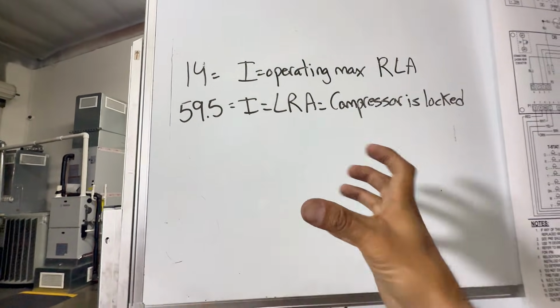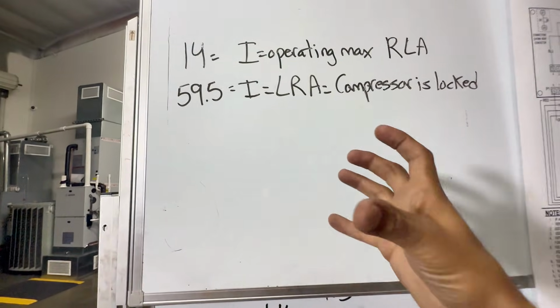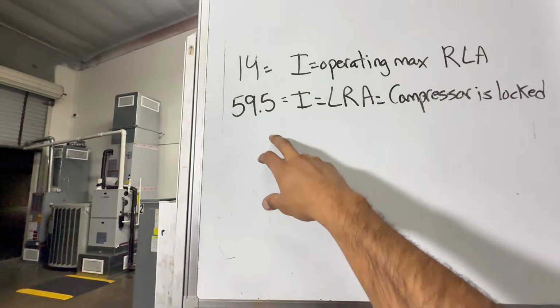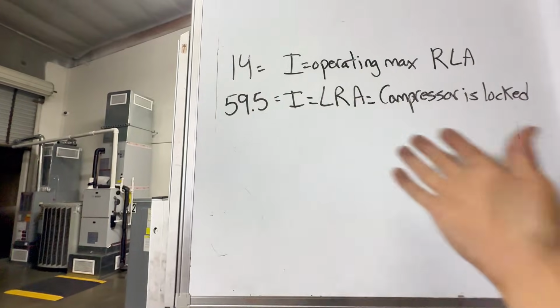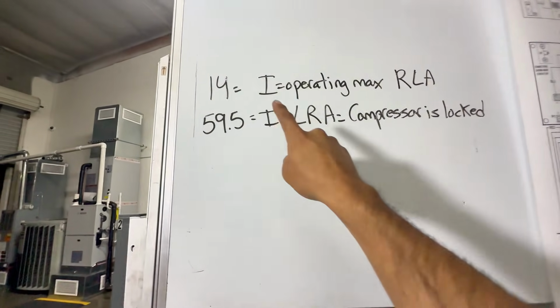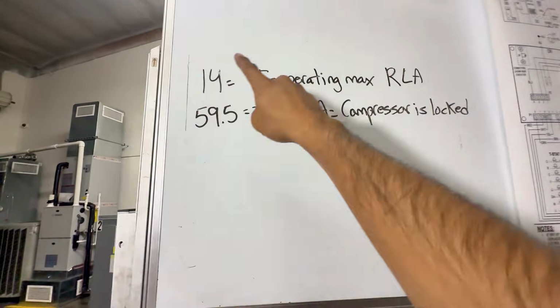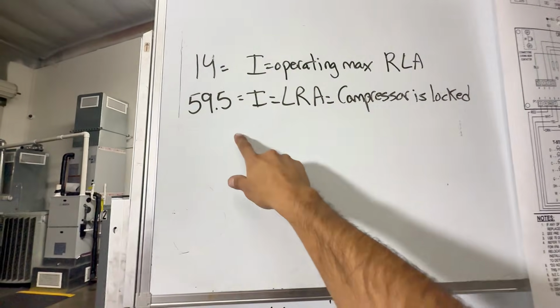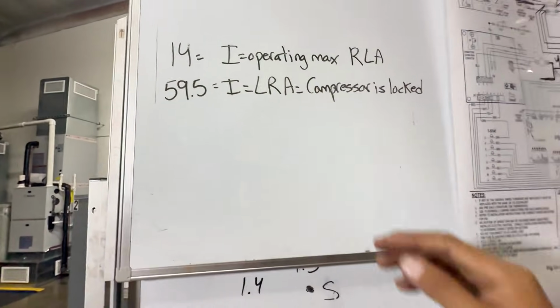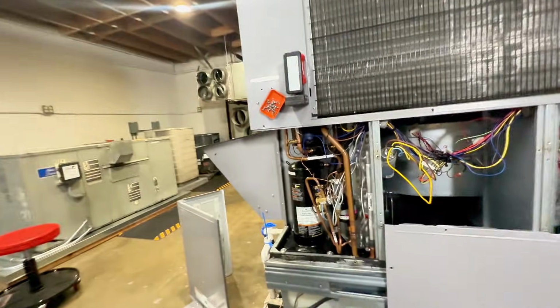And then when the compressor gets stuck and it's not pumping, the rotor is locked, it should be pulling close to 59.5. But this number here is the number we're going to be focusing on today. And I'll show you an example of locked rotor amps as well. But that's what we should be pulling.